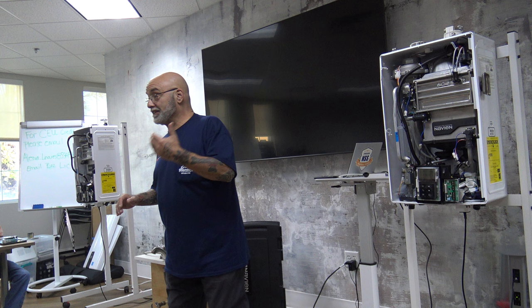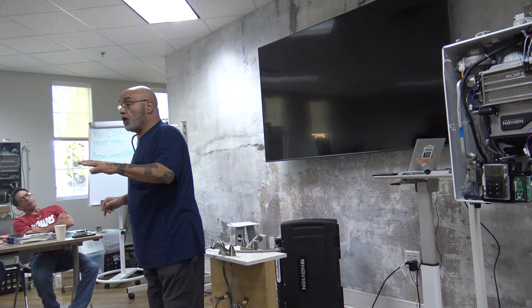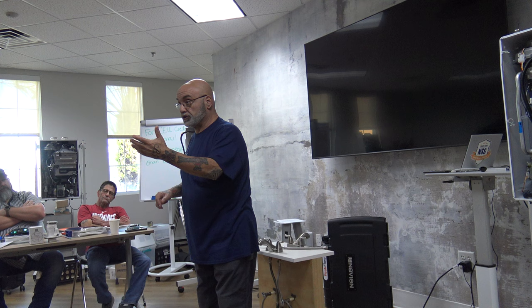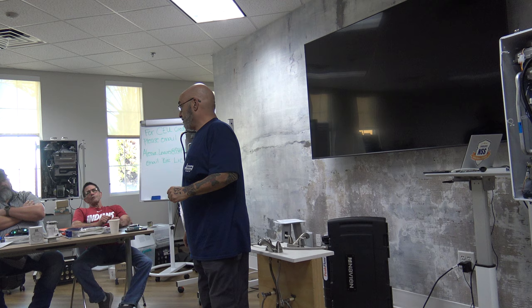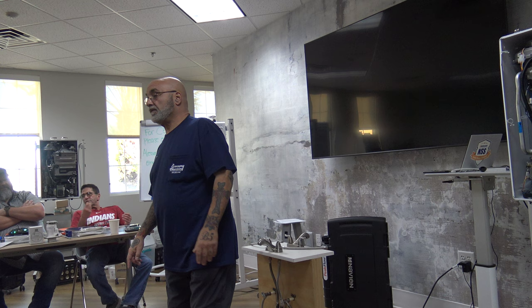Okay, so what do you think is the number one thing that either you have seen or what I have seen through the years of troubleshooting and helping people throughout the world with this? What do you think is the number one? The rust and corrosion from the condensate that drips down on the inside of everything. That's a big one. Water quality? Better than a gold star. Misdiagnosing? Communication? Close. Venting. Venting, okay. Easiest part of it, too. Venting is the biggest problem.